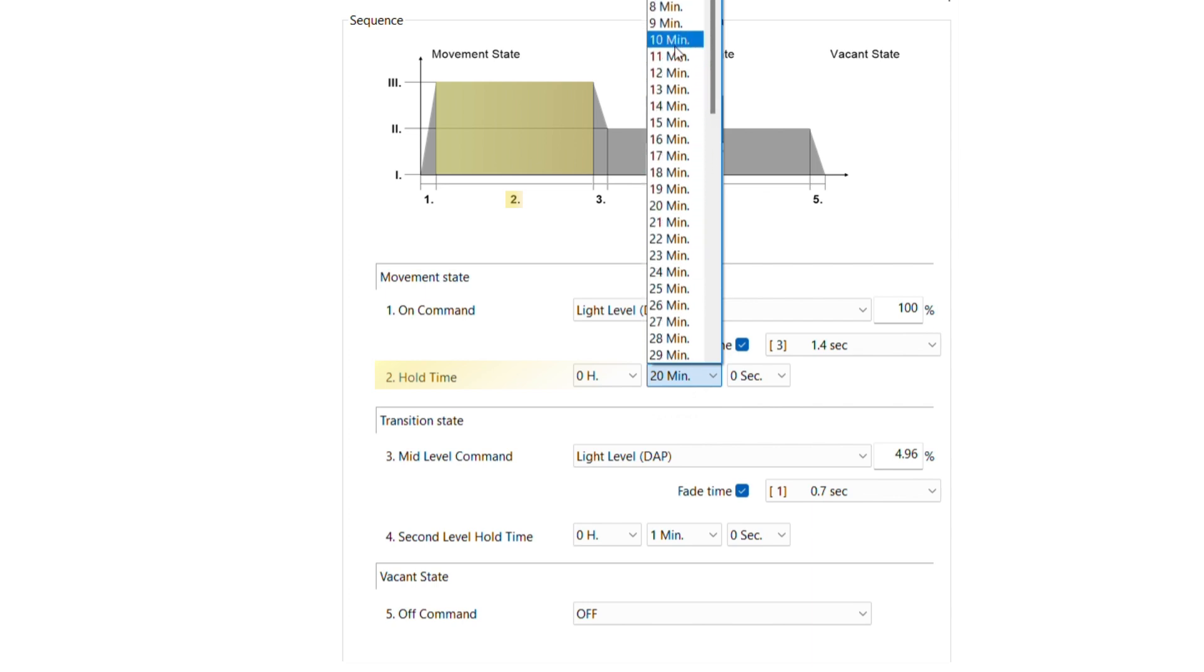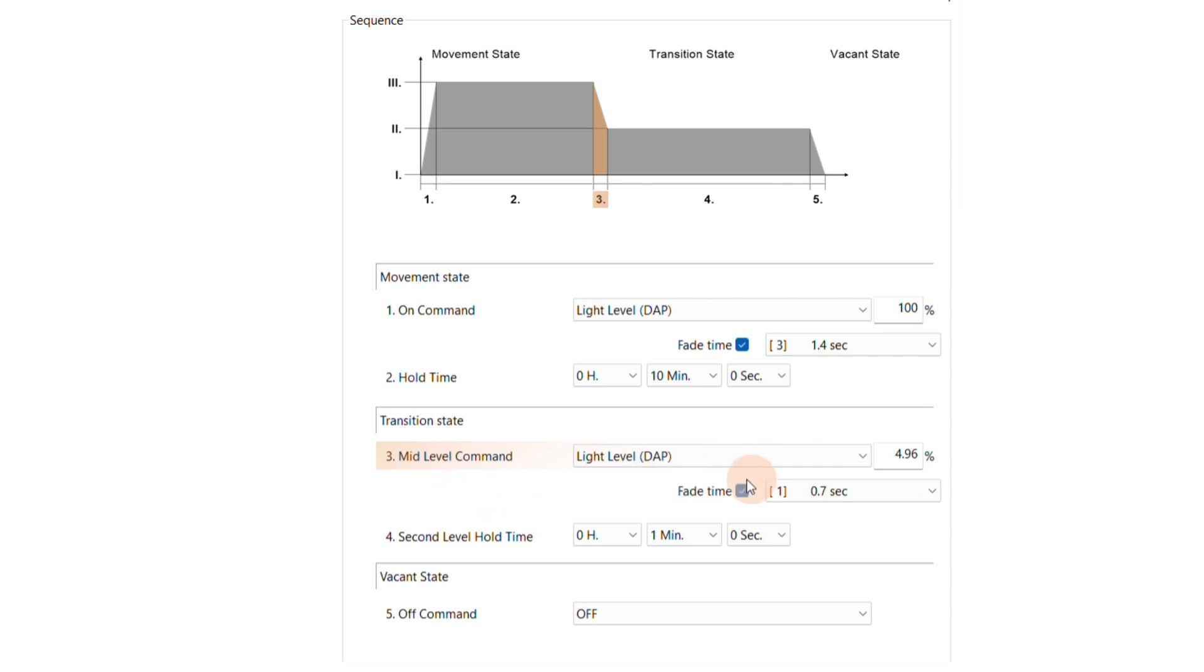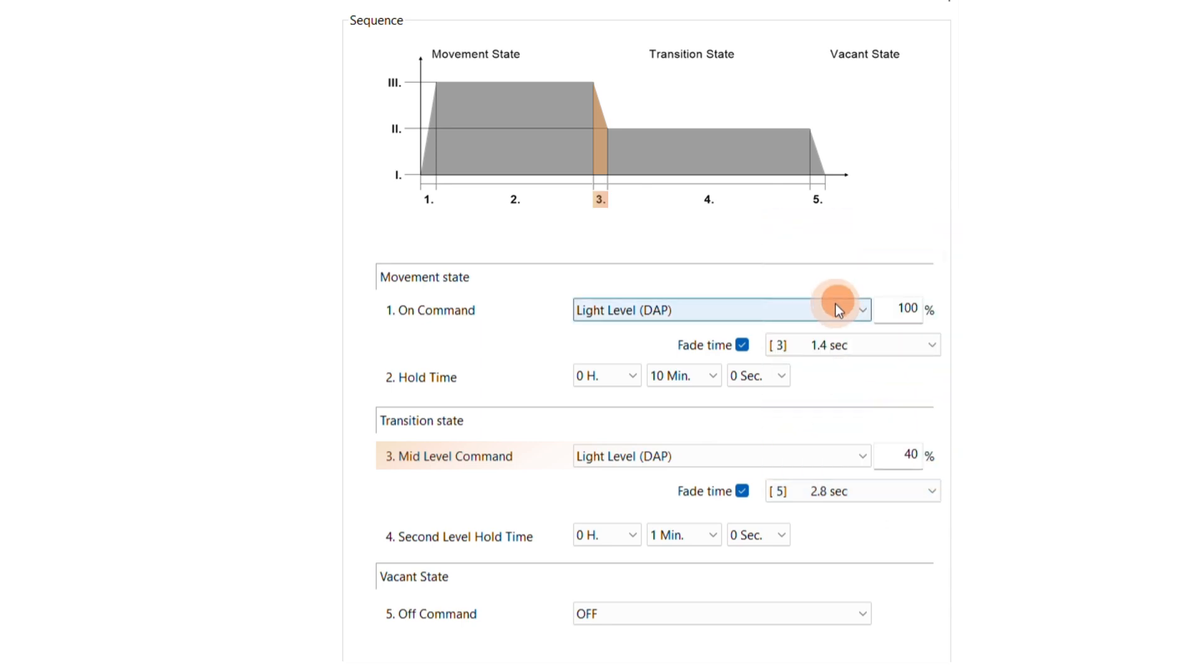If no further motion is detected within the 10 minutes hold time, the sensor will enter the transition state. Here we can set a second light level using the drop-down for mid-level command. We'll use a light level of 40%. Additionally, we will set a fade time of 2.8 seconds to ensure a smooth transition from the first light level of 100% to the second light level of 40%.